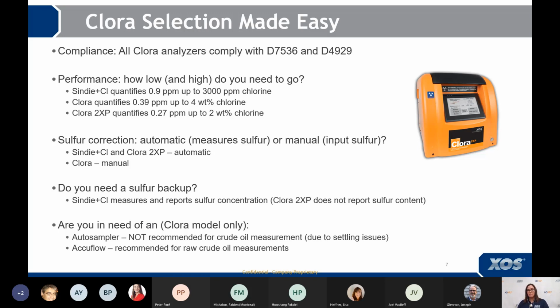Next, you want to consider some accessories and things like that. Like, do you need a sulfur backup? Because our Sindie plus chlorine analyzer will measure and report the sulfur concentration. The Clora 2XP, although it has the automatic sulfur correction, does not report the sulfur content. The sulfur is measured for correction purposes only. And then lastly, you would consider things like autosamplers and AccuFlows.